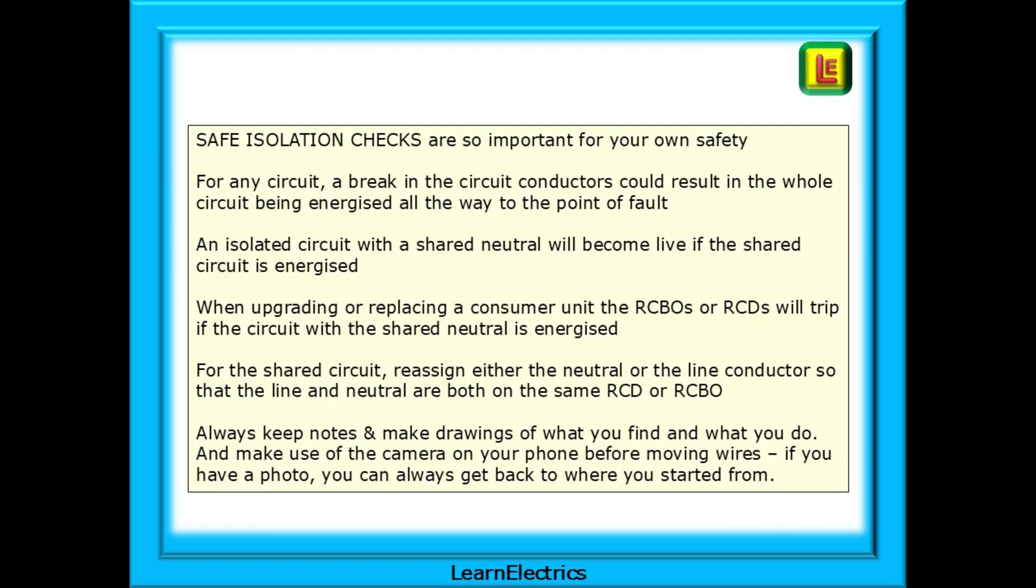A quick recap. Safe isolation checks are so important for your own safety. For any circuit, a break in the circuit conductors could result in the whole circuit being energised all the way to the point of fault. An isolated circuit with a shared neutral would become live if the shared circuit is energised. When upgrading or replacing a consumer unit, the RCBOs or RCDs would trip if the circuit with the shared neutral is energised. For the shared circuit, reassign either the neutral or the line conductor so that the line and neutral are both on the same RCD or RCBO.